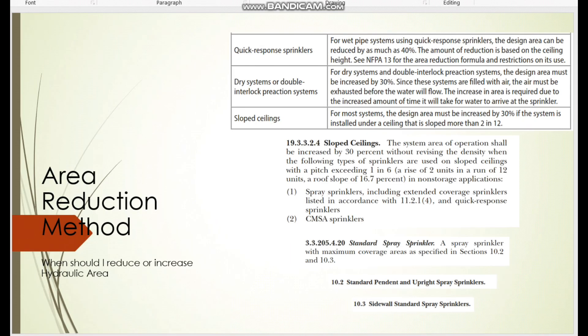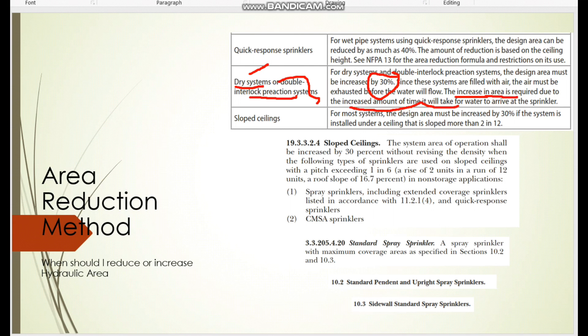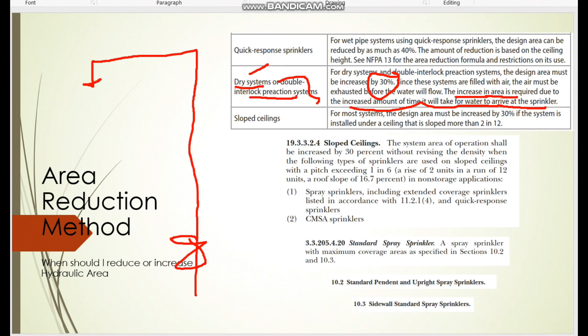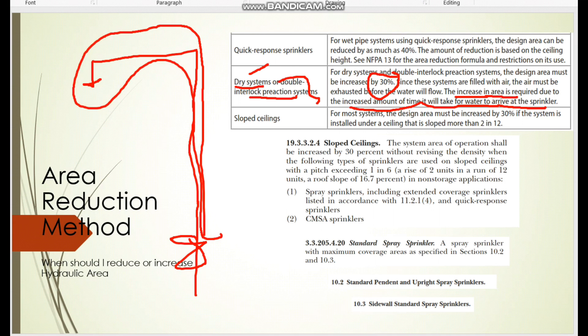The second important condition is for dry systems or double interlock pre-action systems. In a dry system, there is no water above the dry valve — only air — so when a fire occurs the air in the pipe must be expelled before water reaches the sprinkler. Because of this increased travel time, you must increase the hydraulic area by 30 percent for dry or pre-action systems.